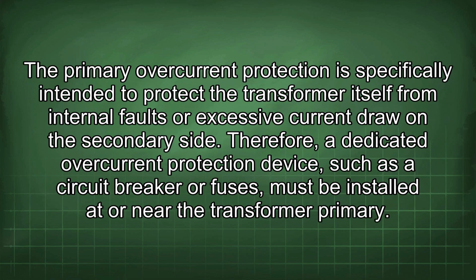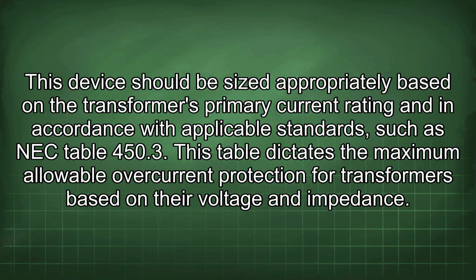The primary overcurrent protection is specifically intended to protect the transformer itself from internal faults or excessive current draw on the secondary side. Therefore, a dedicated overcurrent protection device, such as a circuit breaker or fuses, must be installed at or near the transformer primary. This device should be sized appropriately based on the transformer's primary current rating and in accordance with applicable standards, such as NEC Table 450.3. This table dictates the maximum allowable overcurrent protection for transformers based on their voltage and impedance.